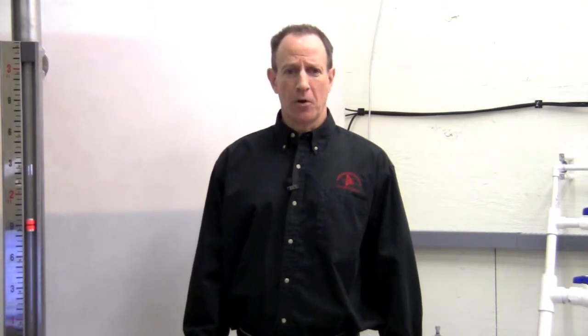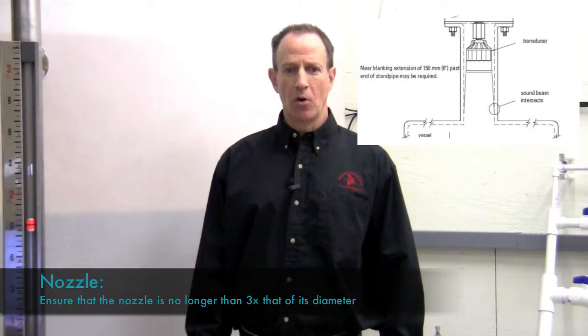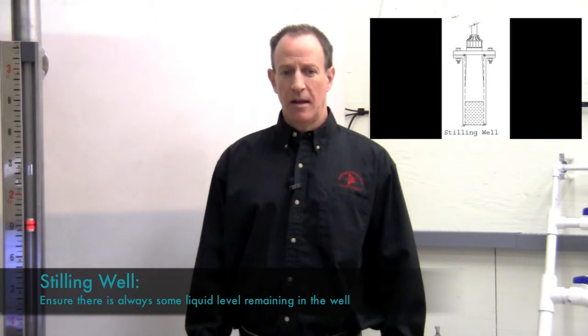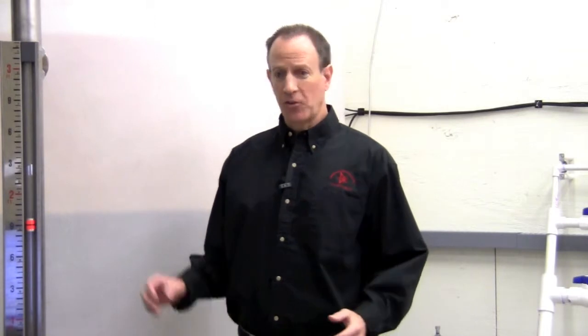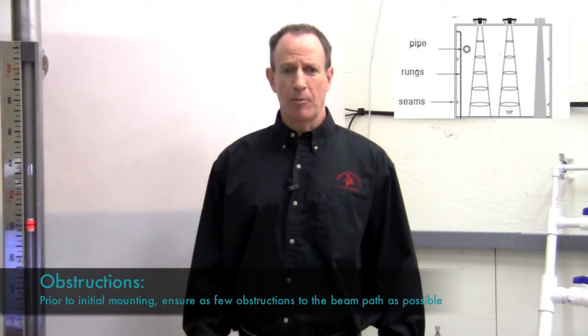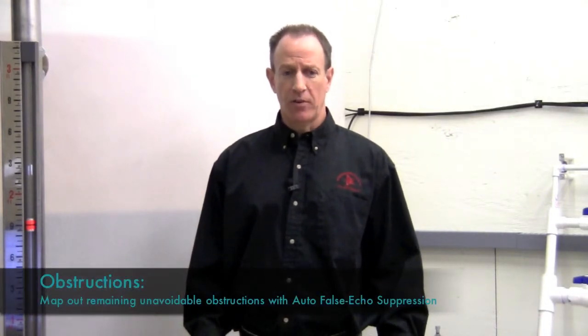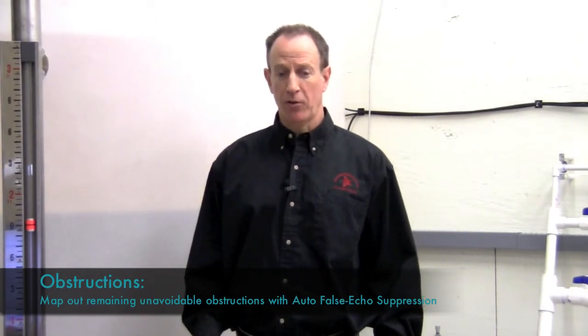Nozzles can create problems with ultrasonic sensors. Siemens suggests any mounting nozzle length be no longer than three times its diameter. Stilling wells are acceptable in many cases, as long as some liquid always remains in the well. Obstructions inside the vessel may cause false reflections, so before mounting the sensor, make sure there aren't any obstructions in the beam path. If you can't get away from all the obstructions, the SITRANS Probe LU may be able to map them out with the auto-false echo suppression function.